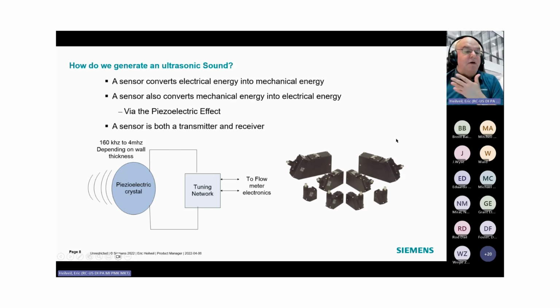So how does it all work? Well, in the transducer, there is a piezo stack. The piezo stack is hit with electricity and it oscillates. That frequency then is transmitted directly to the pipe through either an acoustic mat or an acoustic gel.